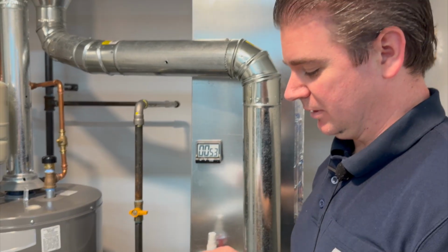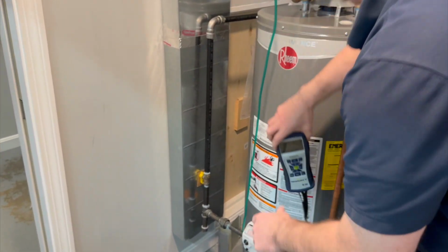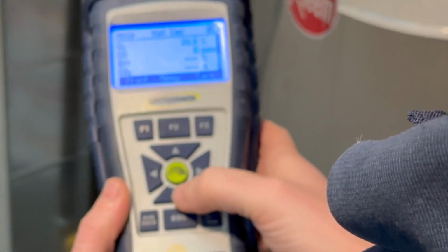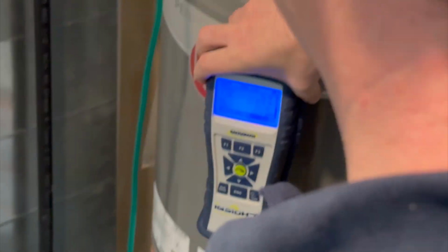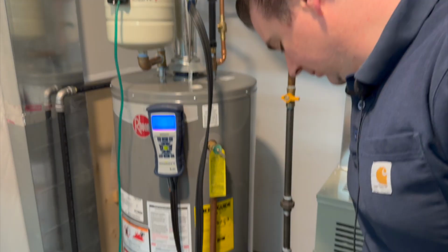Next we're going to test for air-free CO, or carbon monoxide air-free, at 5 minutes. I'm going to get my combustion analyzer set up. Slid on down. Turn the backlight on. I'm going to scroll down, hit the down button 4 times until I get to carbon monoxide air-free at the very bottom. Hit the run button. Now while I'm waiting for that, completed item, my CO monitor says 0 parts per million.